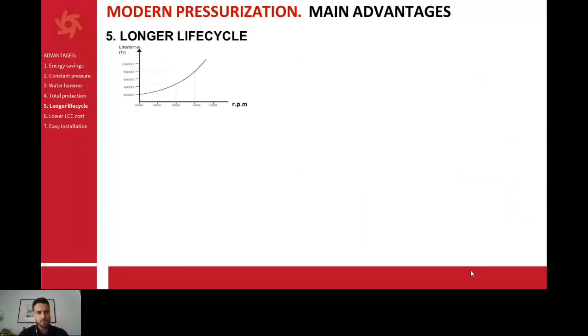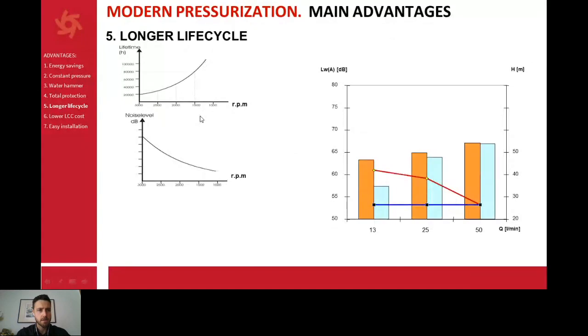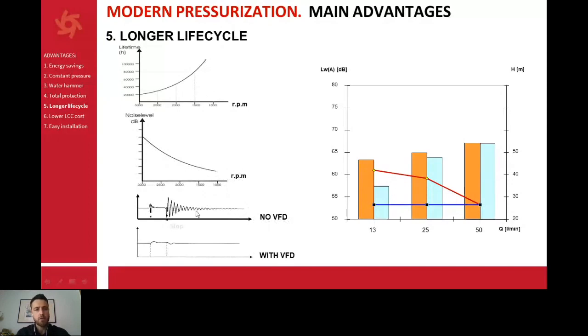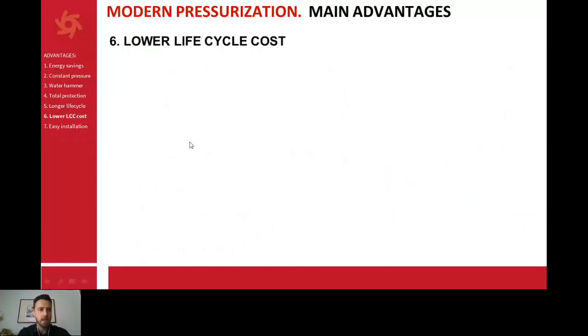Longer life cycle. What's this? As we have fewer revolutions per minute, we have a longer lifetime of the pump because of the spinning of the pump. The wear is less. Noise level. As we have fewer revolutions, the noise also goes down. And the oscillations. With no variable frequency drive, we have many oscillations in the system. Meanwhile, if we have the variable frequency drive, we have no oscillation. Constant pressure. It's better for all the systems. And lower LCC, life cycle cost.